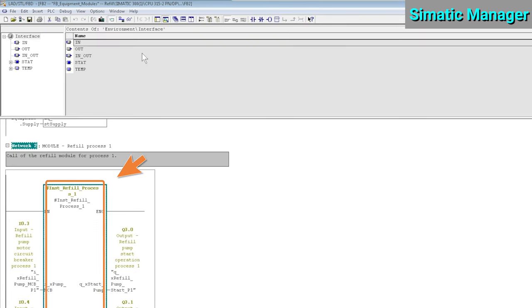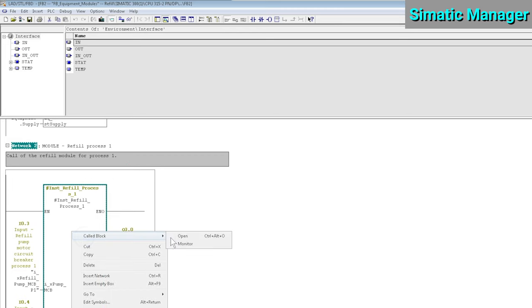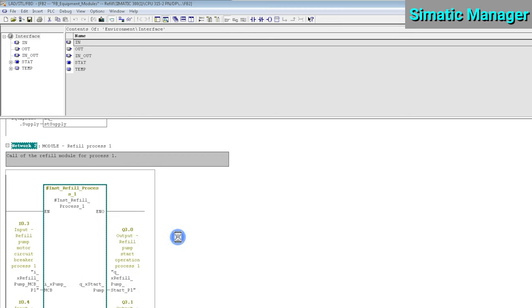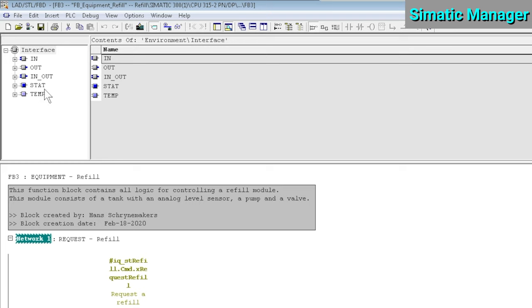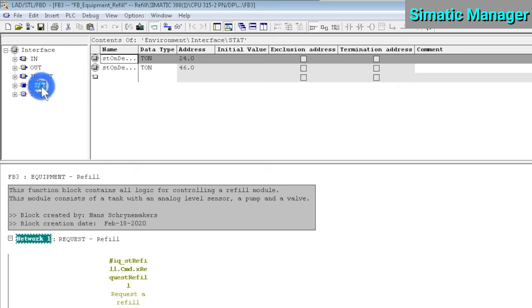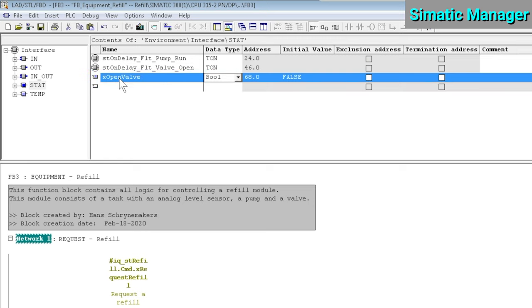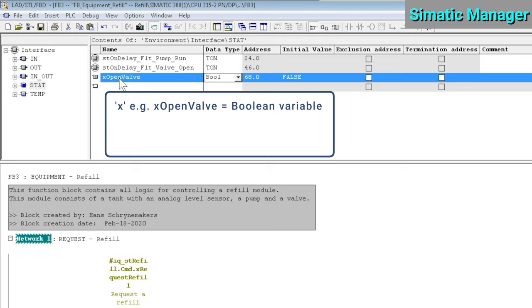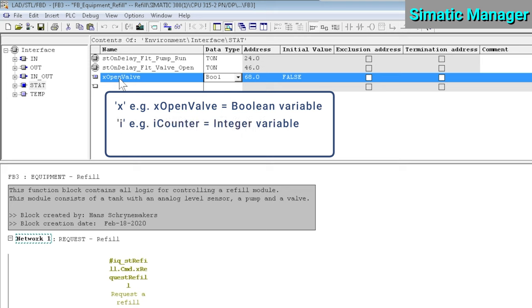Let's have a look at an example to clarify this. Here in Network 2, we have a function block called FB Equipment Refill. Let's open this function block and add, for example, a new static variable to the block interface. So here I'm adding a new boolean variable called OpenValve. You can see that I've added a lowercase letter X in front of the variable name to indicate that this variable is boolean. For integers, I would use a lowercase i, for reals a lowercase r, etc.